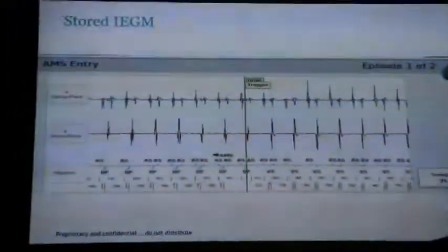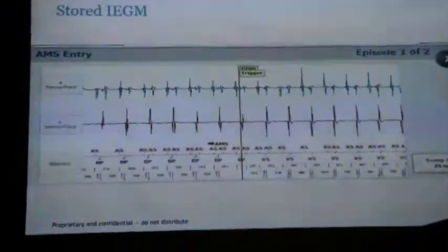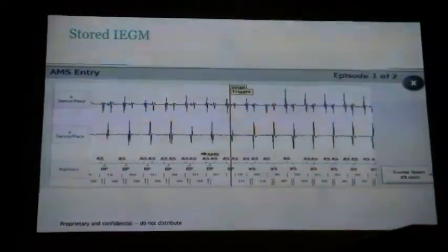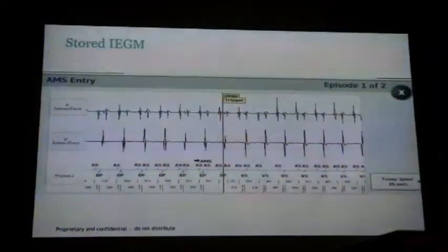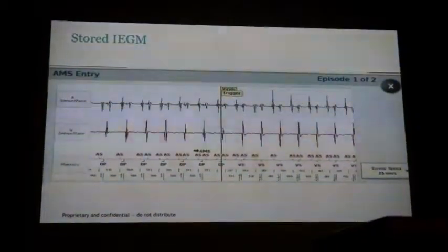So I would definitely be looking at the P wave amplitude at implant, but if there is far field you want to look at that in two configurations: A sense V sense, and A sense V pace, because it can change, okay?